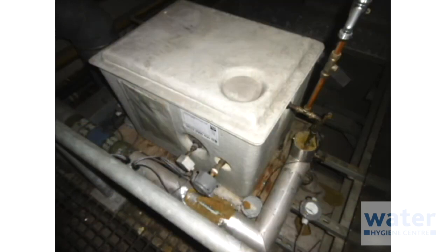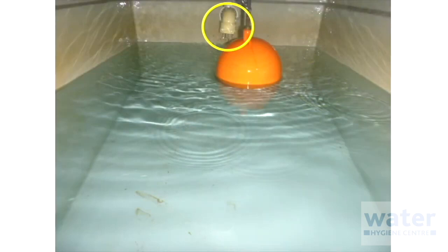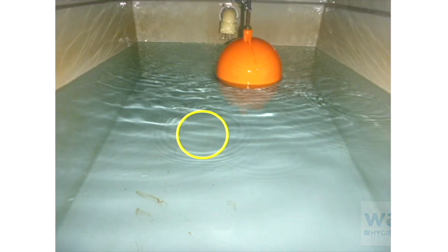Finally, let's look at taking temperatures from a cold water storage tank. The first temperature needed is the supply temperature to the tank itself. This can be taken from the supply pipe or from the water at the valve outlet. The second temperature is taken from the water stored within the tank. Ensure that the immersion probe is clean before submerging it into the tank water.